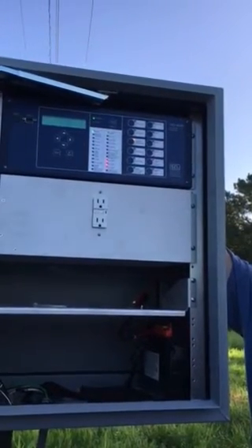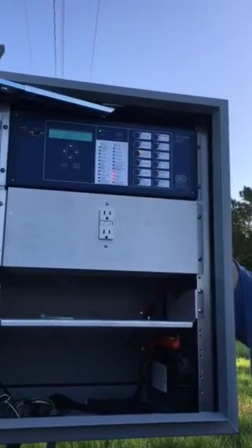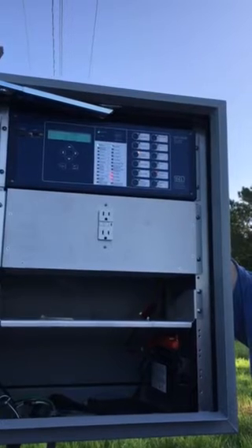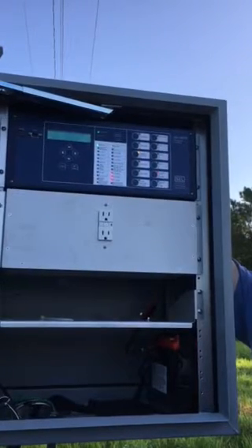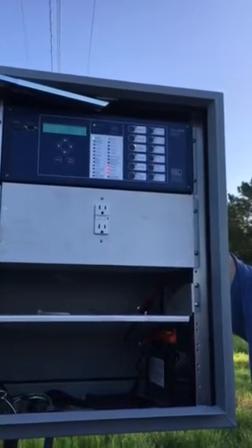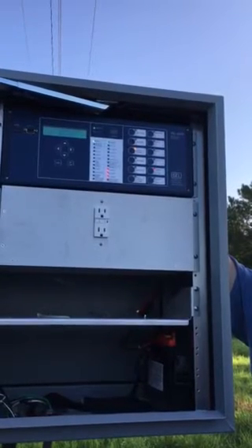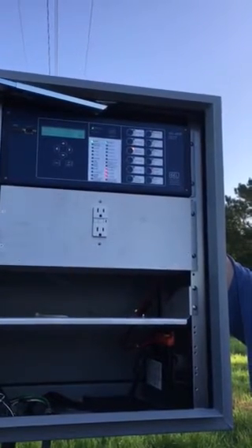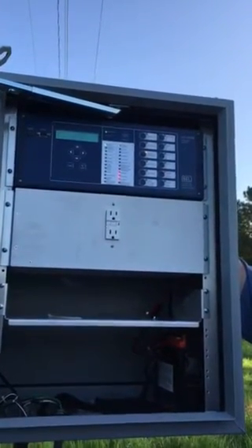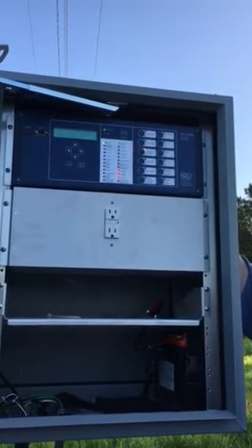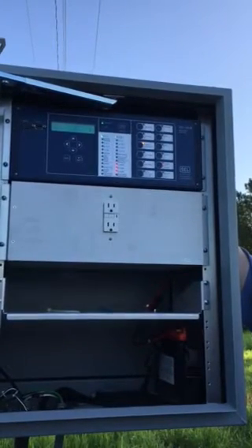So if that station breaker blinks, just say a tree limb bumped and it blinks the station, it's timed in here, and it's set up to open after the second open of the station breaker. It won't do it on the first shot. It sees the amps and they got so much time set in it that it's going to wait till the second shot to open up, because if that first shot burns it off, they don't want to take it offline.